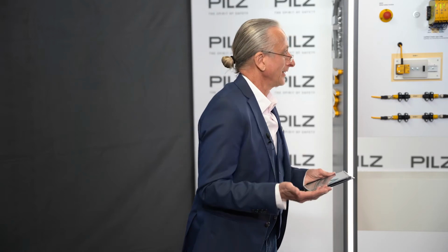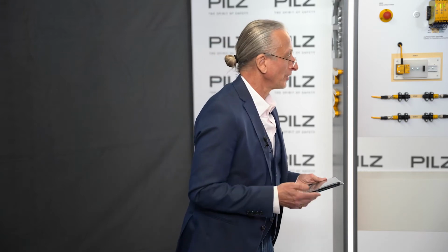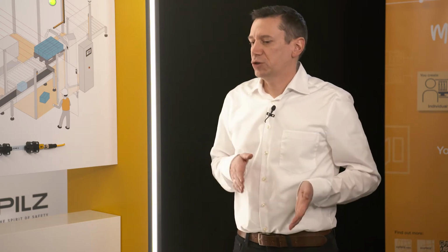That's great. Steffen, myPNOZ offers a global safety function via the head module. And additional safety zones can also be monitored. How does this work exactly? And can you show us this in action again? Sure. So safety zones means that there can be different areas in a machine or in a system, and these areas actually run independently of each other. For instance, if you need to switch off one area because a safety requirement has been violated, this does not mean that the entire application has to be switched off, but only this area.